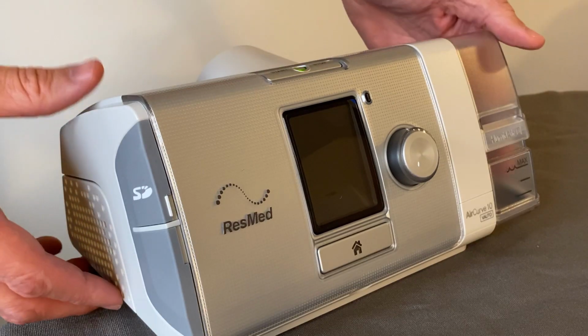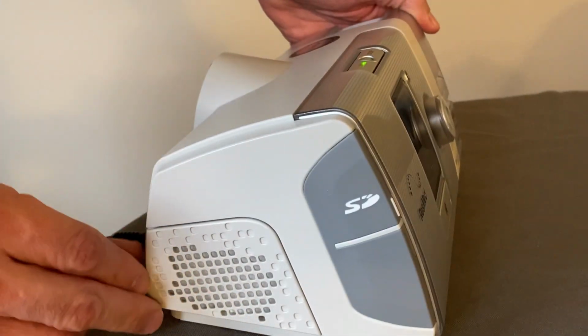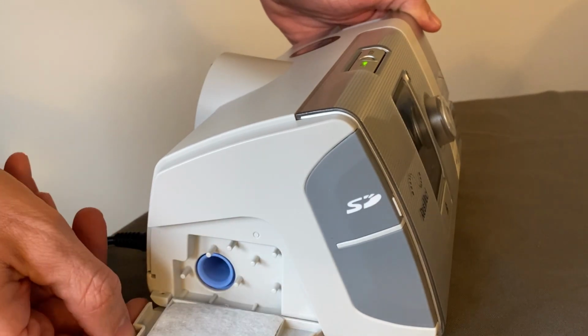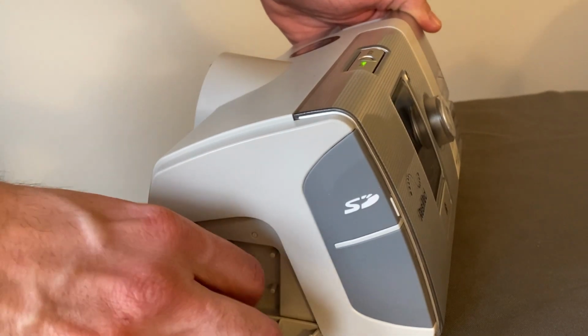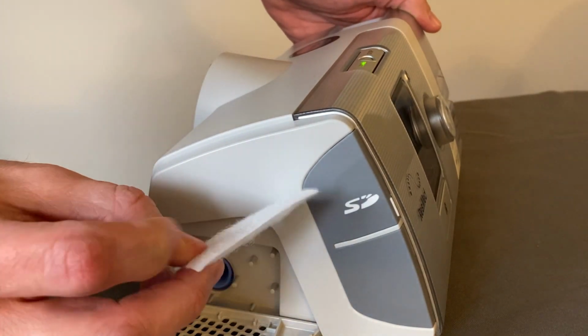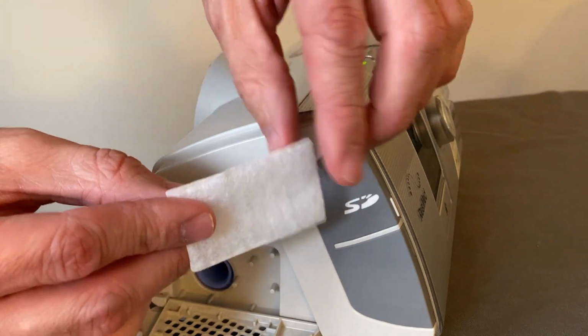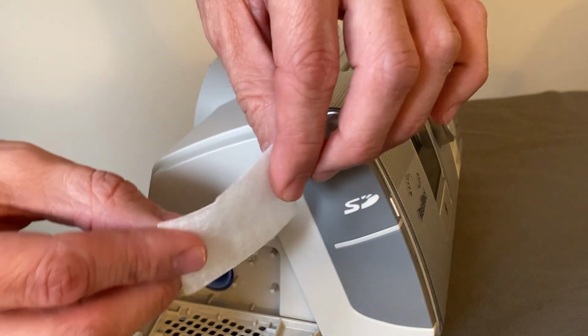Filters are an important part of maintaining your BiPAP machine. They prevent dirt and dust from collecting and entering into either machine parts or your tubing. Filters should be inspected regularly and replaced when damaged, discolored, or wet. To access the filters on the AirCurve, look for the vented panel on the left-hand side of the machine. Pull the panel open to inspect or replace the fine filter. The fine filters for the AirCurve are disposable and should be replaced every month or as needed.